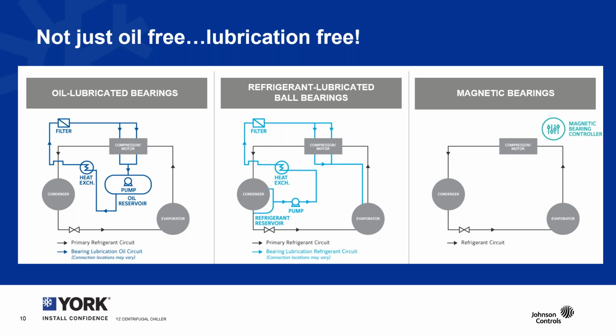The removal of all of the lubrication system means all of that complexity is reduced down to a sophisticated magnetic bearing system that has the kind of durability that navies around the world depend on for a superior chiller. And that simplicity is the key to not only durability, but reducing the maintenance, which is, I think, what really delights customers with commercial chillers. So that lubrication-free, non-contact design of the YZ chiller provides system simplicity. It provides reliability that's far beyond any continuous contact bearing, whether it be lubricated with oil or lubricated with refrigerant.